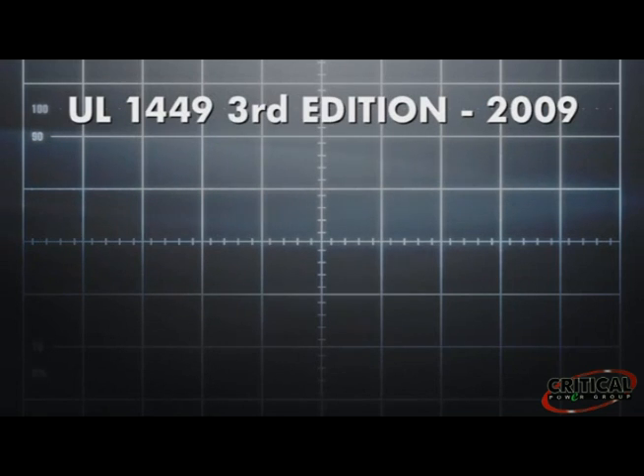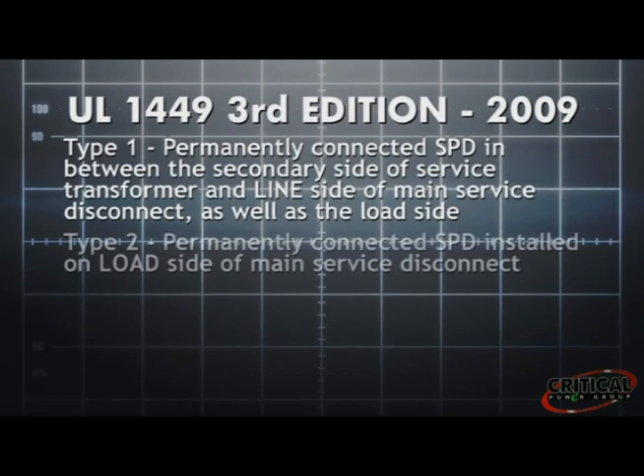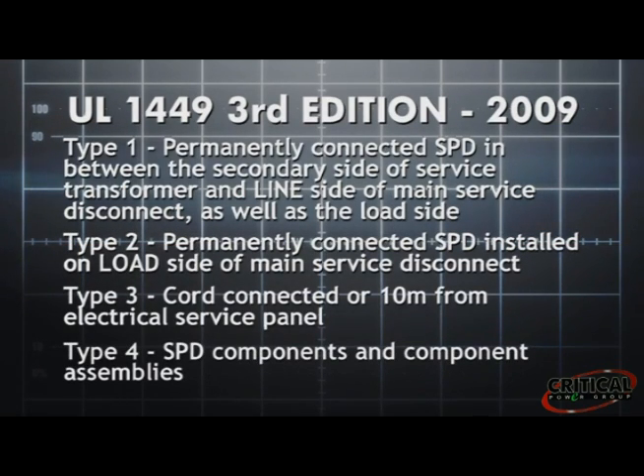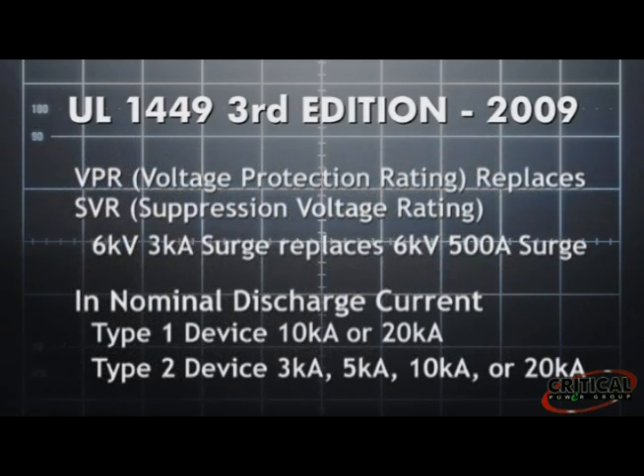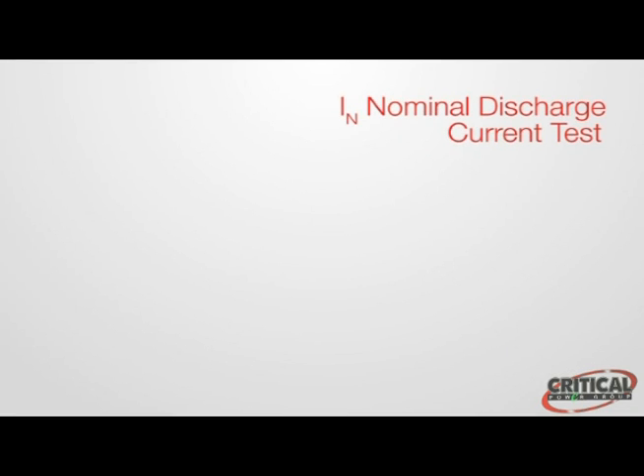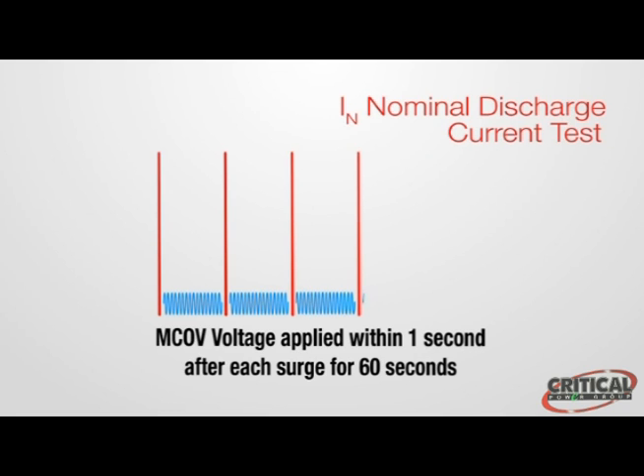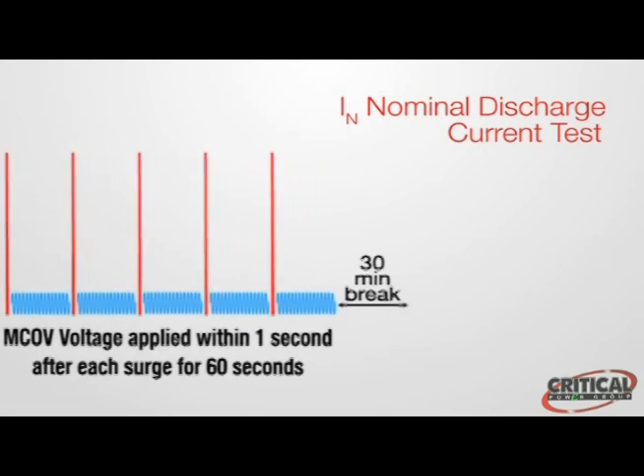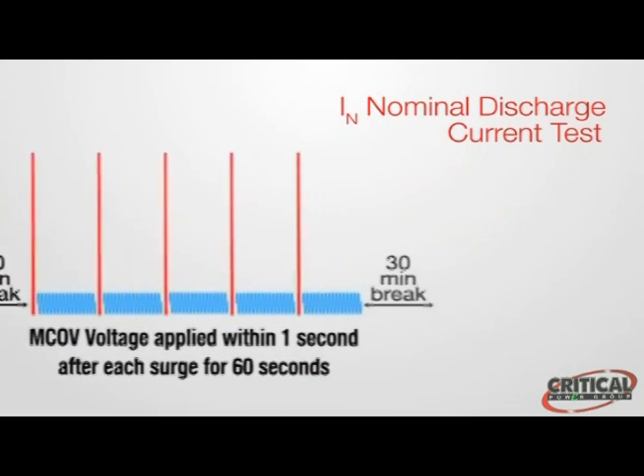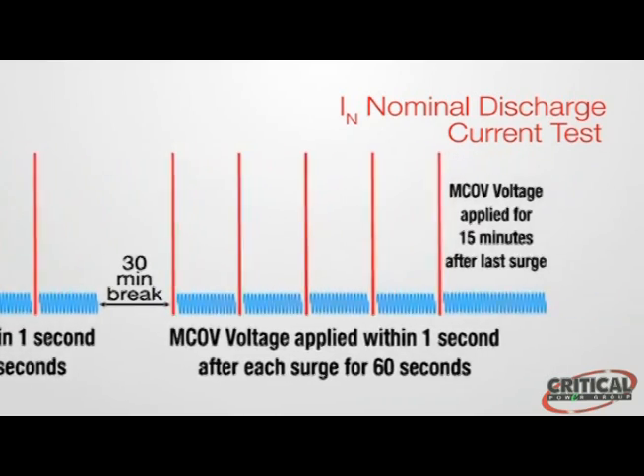UL 1449 3rd edition, which becomes effective September 29, 2009, creates 4 categories of SPDs. Current Technology's Catastrophic Protection System already meets these standards as a Type 1 SPD. UL 1449 3rd edition also establishes a new test to ensure product integrity by stressing the SPD to determine whether any significant amount of degradation will occur. This is called the nominal discharge current test, and it stresses the SPD with a total of 15 transients in 3 phases, at a nominal discharge current selected by the manufacturer. The voltage protection rating is measured before and after the test, and the results must not vary by more than 10%.